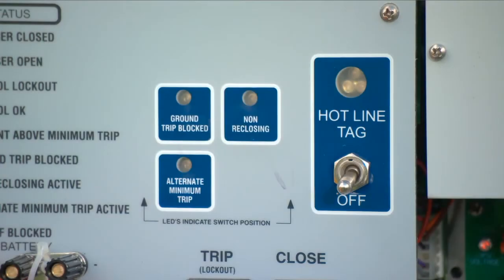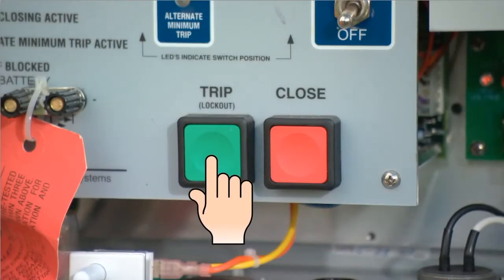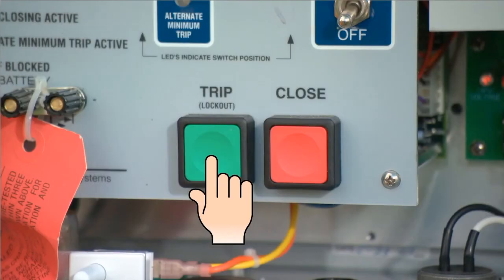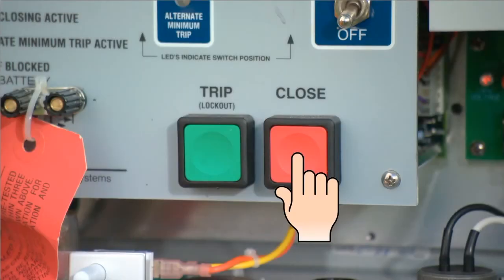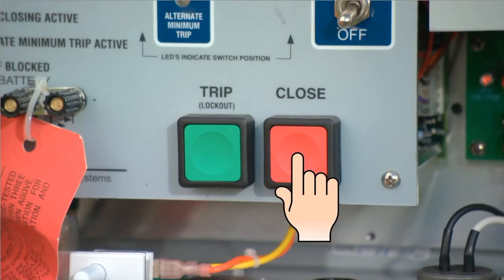Alternate minimum trip. This switch permits switching to alternate pre-programmed phase, ground, and sensitive ground fault minimum trip values. Trip or lockout and close switches. Pressing the green trip switch opens the recloser, and the control locks out. Pressing the red close button returns the recloser to the reset condition, and the recloser closes.